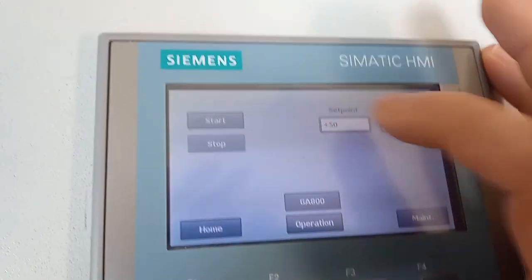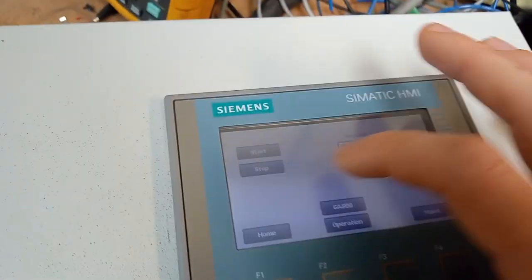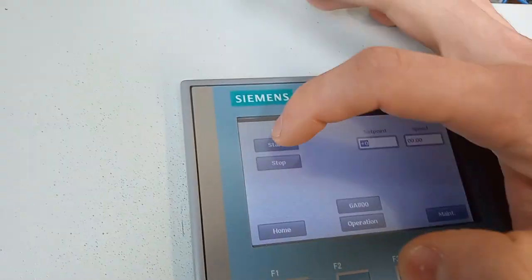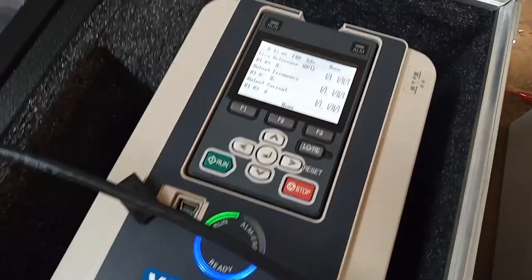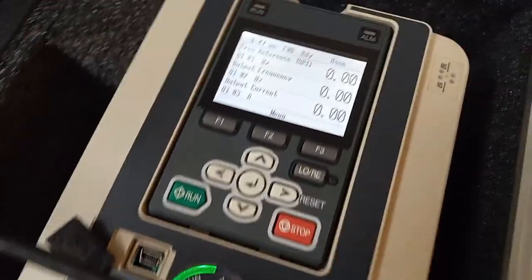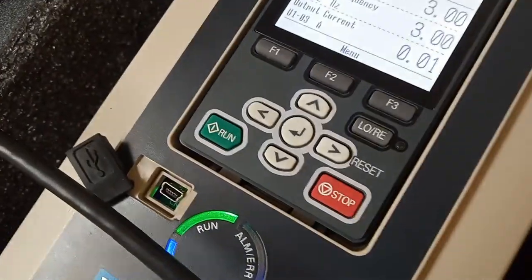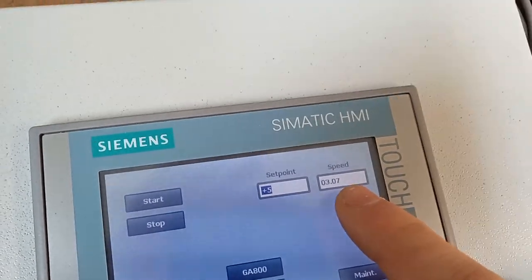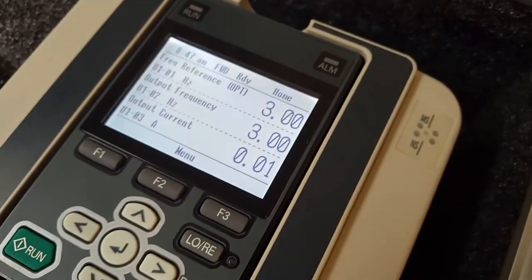Now we're going to hit the stop button. I'm going to show something kind of neat. Might help you troubleshoot it later on. So if I come over here and I give it a zero speed reference and I hit run or the start button right here, nothing, nothing's moving. You see that the output speed isn't on and the run light is just going to sit there flashing, saying I'm ready to run, but you ain't telling me nothing. I'm just going to run at zero since you told me to run at zero. So there's the drive. It's running at zero. Now let's give it a little speed reference, 5%. There it goes. It's going to run at 5%, and that's actually how many Hertz it's running at. 3.07, 2.98. It's going to match up to this, try to come together to tell you what the actual speed on the drive is. Hit the stop button.